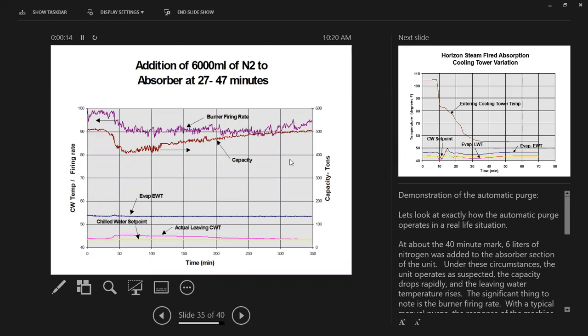That's like if you had a leak, and you can see burner firing rate goes down, capacity goes down, but basically they're showing the evaporator temperature. You know, I mean, it did a pretty good job. What they're showing here is that the controls handled the addition of 6,000 milliliters of nitrogen to the absorber at 27 to 47 minutes. So back in here, and then you look and see what the data on the machine looked like. So it handled it pretty well.